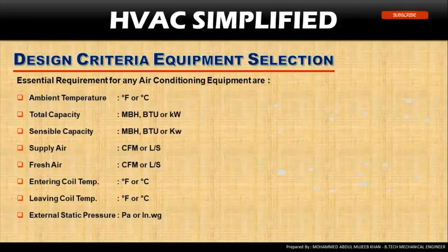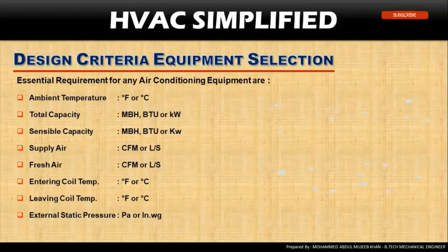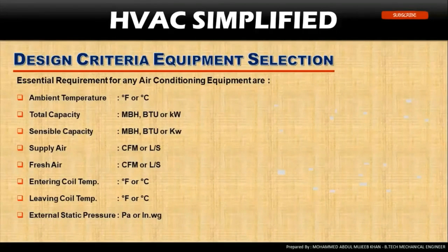External static pressure is required to select any HVAC equipment — including fans, blowers — and for sizing the motor. It is usually calculated for the longest route of the HVAC duct, while the internal static pressure is calculated by the software or any HVAC supplier.